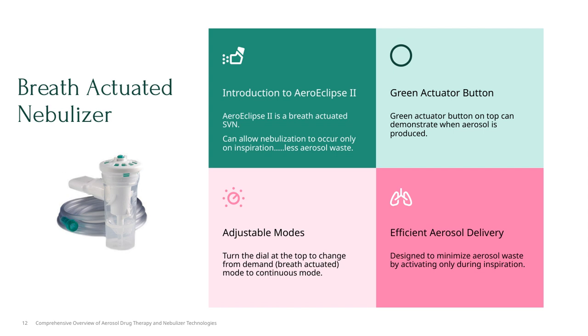The breath-actuated feature is especially beneficial because it ensures medication is delivered only when the patient inhales, reducing unnecessary aerosol dispersion. You'll also notice a green actuator button on top. This button serves as a visual cue. It indicates when aerosol is being produced, so you can quickly verify proper operation.